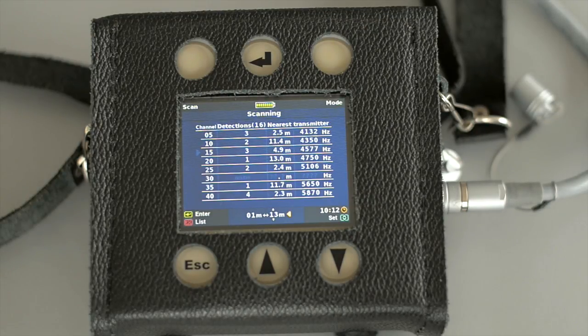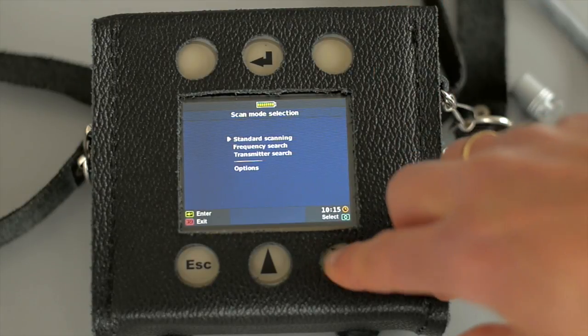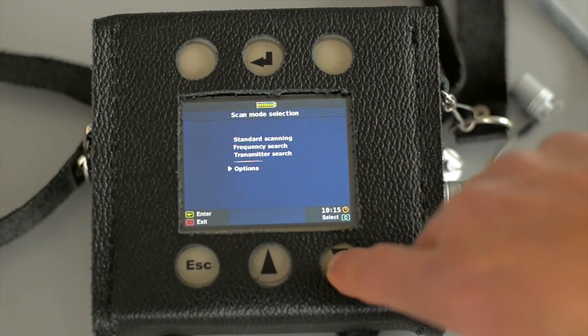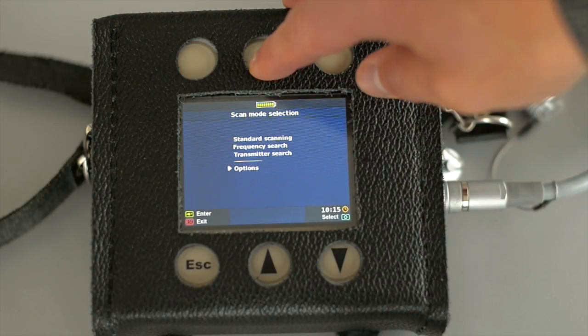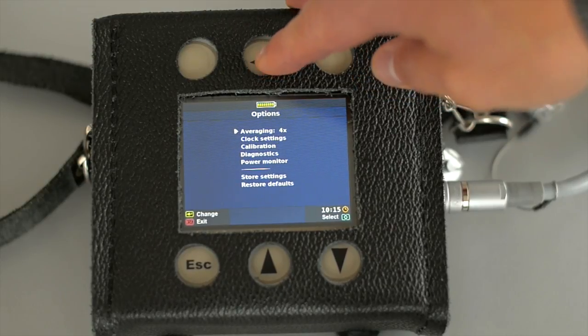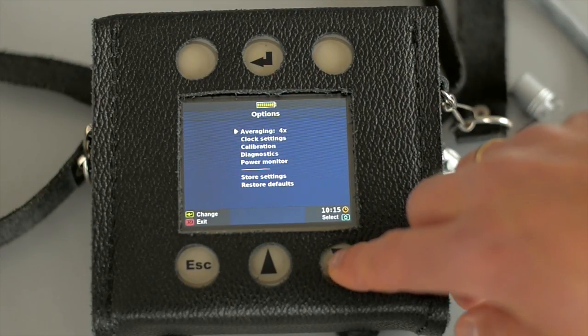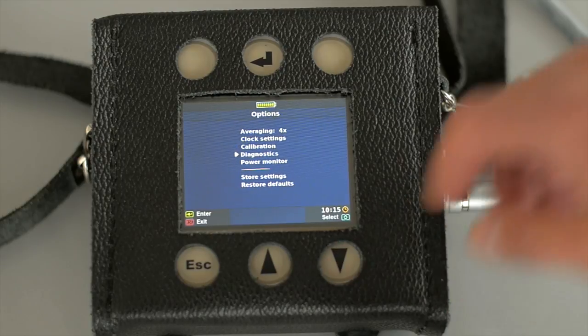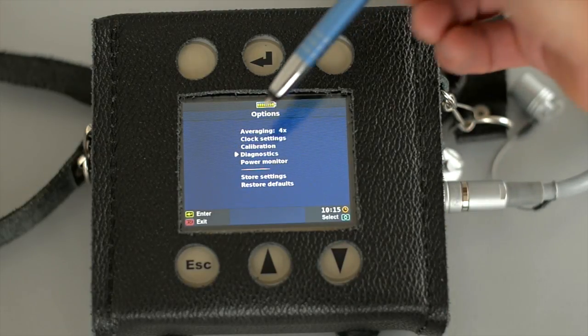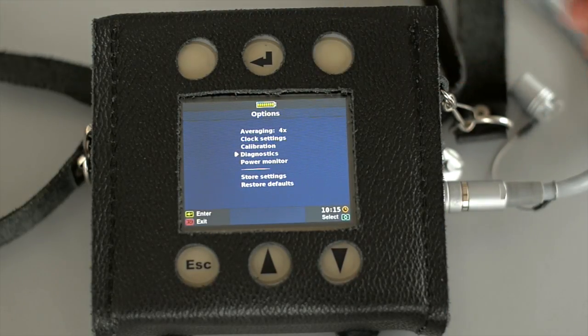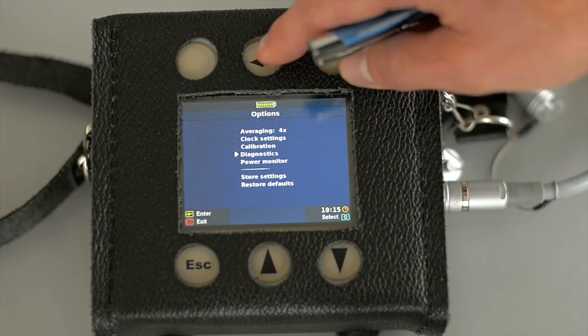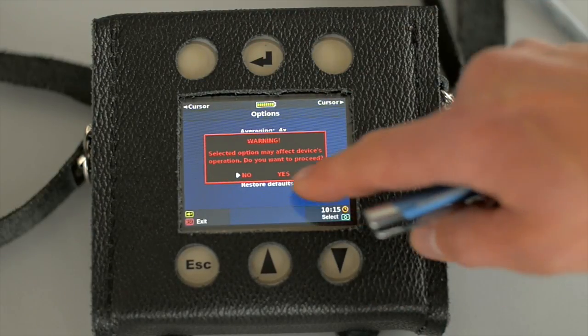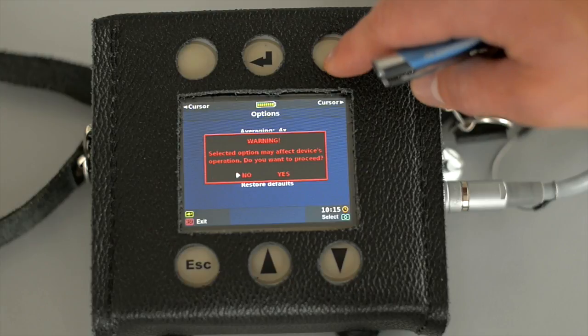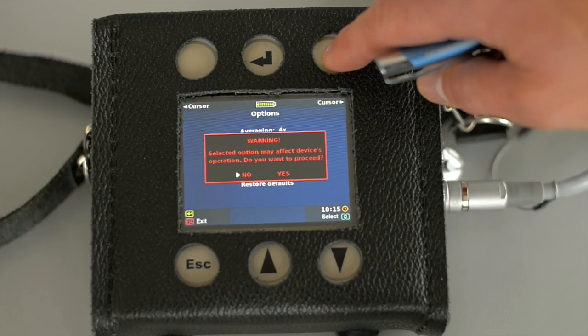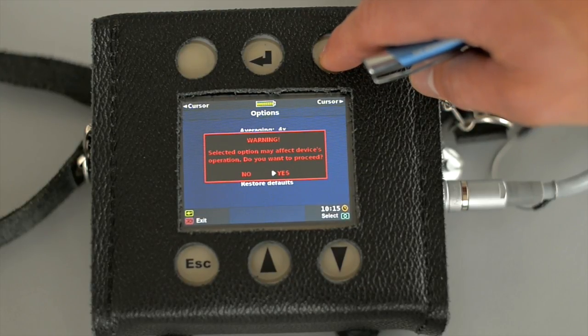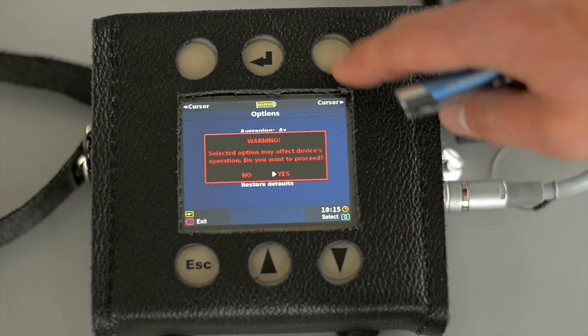calibration. Now we'll show you the option called Diagnostics. It checks if the antenna is correct, and also it needs to be performed if we use a new antenna or an antenna from another device. We enter the option by pressing the mode key and choosing Options and then Diagnostics. We also get a warning here because, as it was with the calibration, this option may lead to improper operation of the device if performed incorrectly.